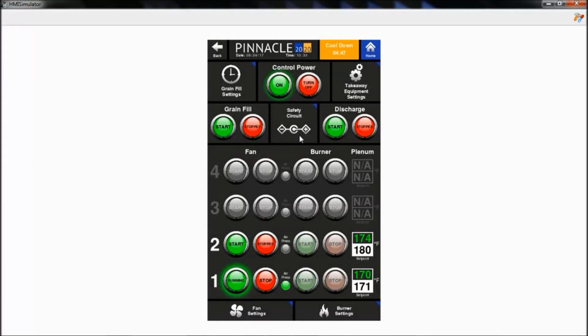If we close that window, a couple of things to note. First thing we see is that the alarm reset button has turned into a cool down timer. If we look at what's still active, we can see we haven't lost control power yet, but the discharge that was running turned off, the burner that was running turned off, but the fan is still running. So when you enter a cool down mode, the way that we're going to handle that is everything besides the fans is turned off, and the fans will continue to run until the cool down timer gets down to 0, at which point the fan as well as the control power will disengage.